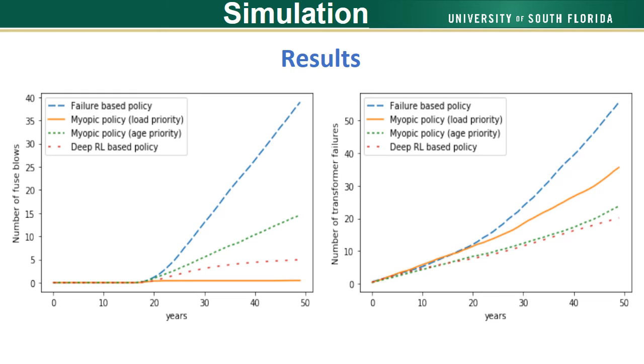We compare four policies. The failure-based policy is the baseline one, which only replaces a transformer by the same capacity once it has failed. This policy does not do upgrades, thus fails to cope with EV inclusion and results in excessive fuse blow and transformer failure events. The myopic policies upgrade or replace the transformer yearly based on some predetermined thresholds on load and age. The myopic policy that prioritizes load over age performs well to reduce the number of fuse blows, but the number of transformer failures is high. The other myopic policy that prioritizes age over load performs well to reduce the number of transformer failures, however, fails to control fuse blows. The deep RL based policy performs better than any of the policies.